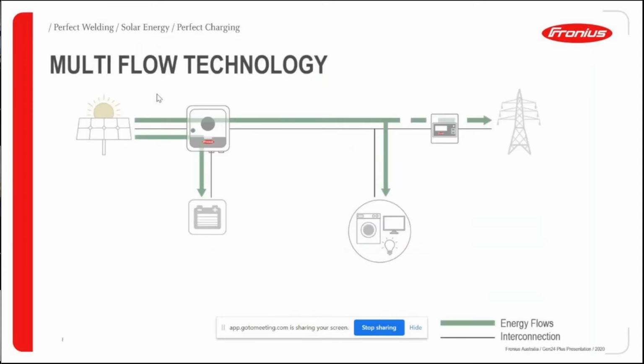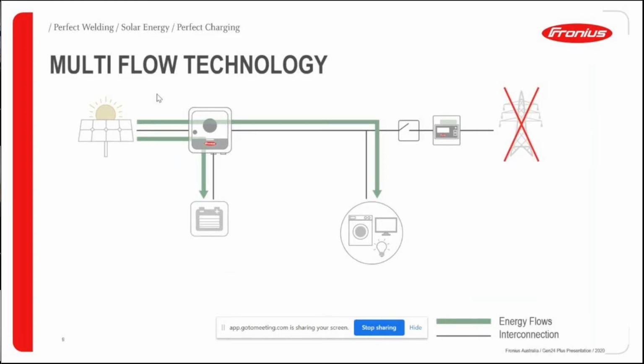All right, so with the Gen24, Fronius has spent quite a few years on research and development to develop this new Gen24 product, so it's got very efficient multi-flow technology. What does multi-flow technology mean? It just means it's able to supply the loads at the same time it's charging the battery or discharging from the battery. So even when the grid goes down, you're still able to charge the battery from the solar and supply the loads in backup mode, because it's using DC coupled technology.